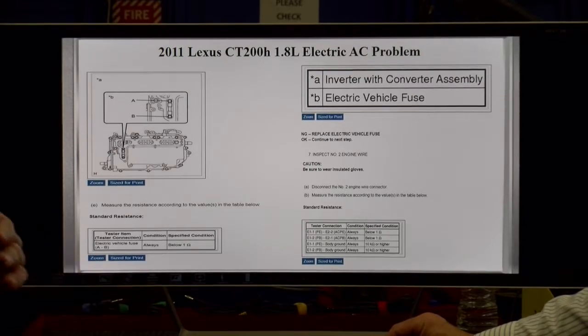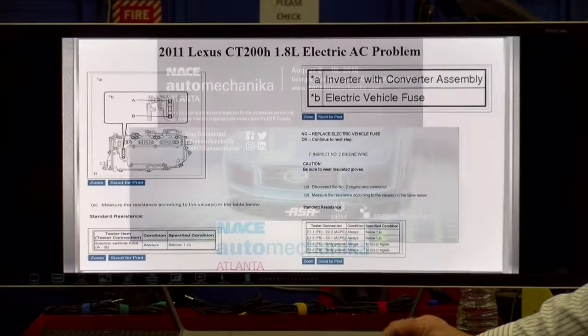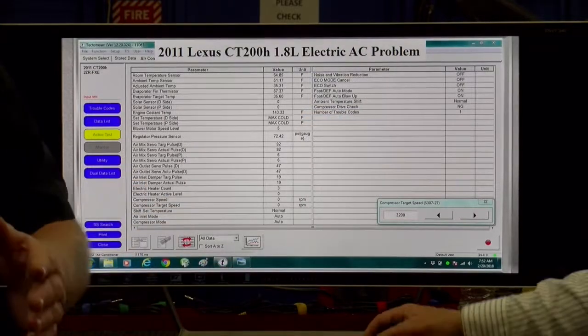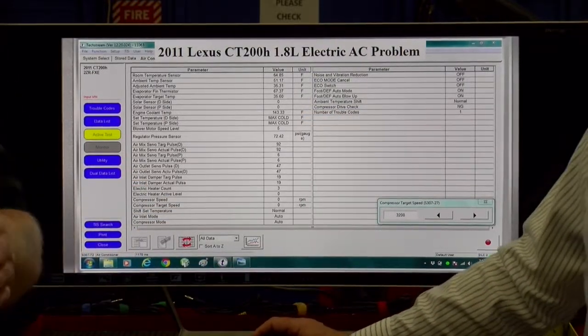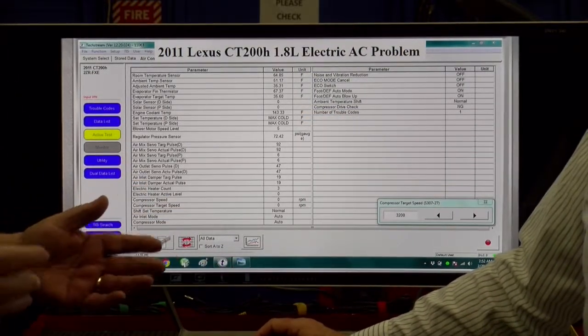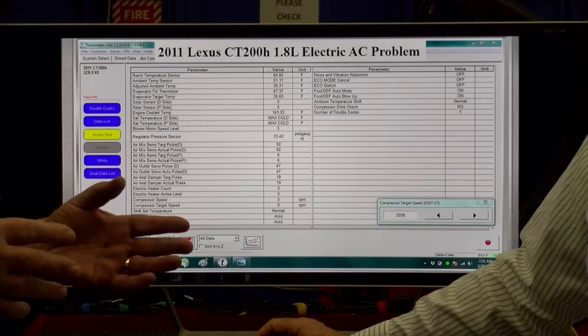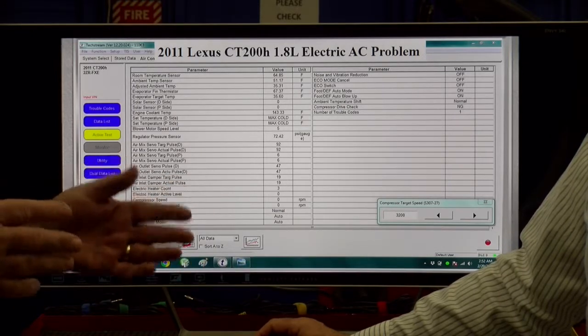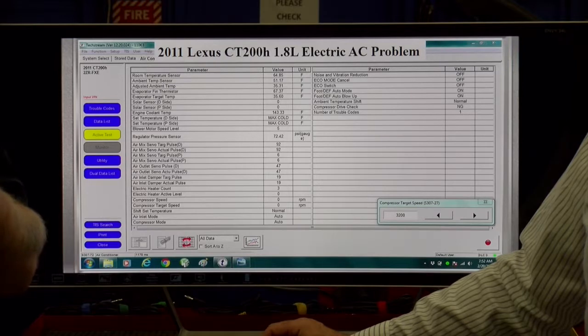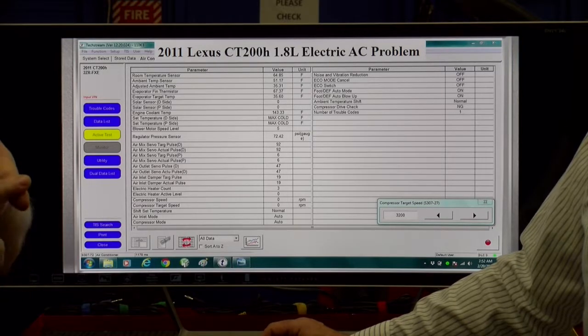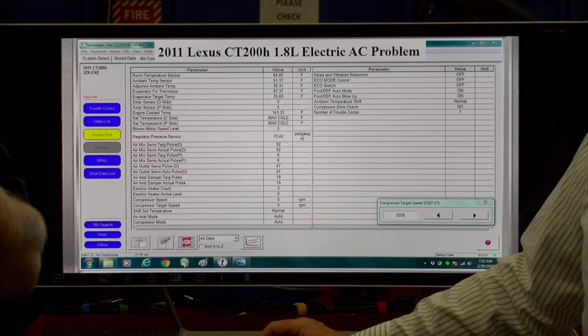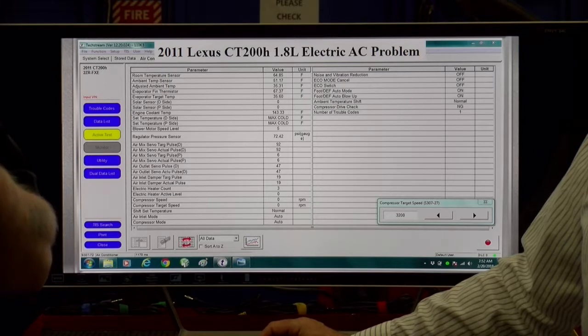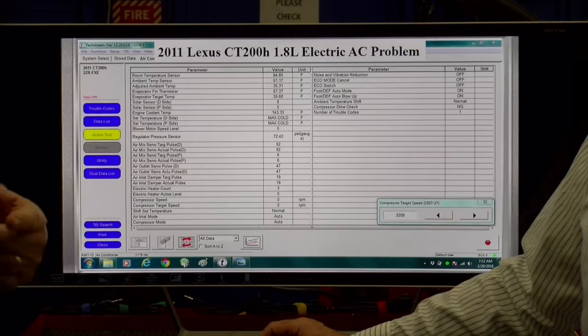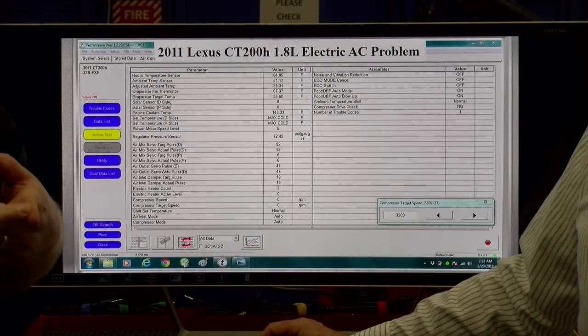I want to interject this as well. You heard mention that if you're not already familiar, if you're going to do any measurements on these high voltage systems, you need a meter capable of doing that, Cat 3 or higher, 1,000 volts AC rated. Not just the meter, the leads you're using also have to be rated Cat 3. And wear your gloves when you're doing this, absolutely.